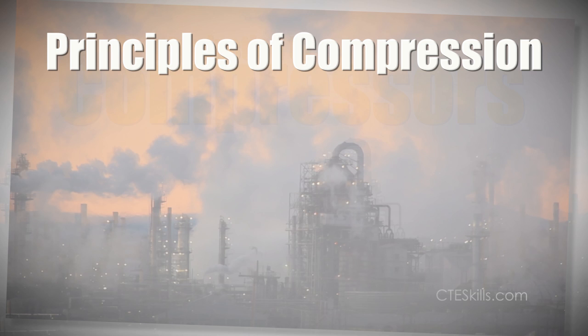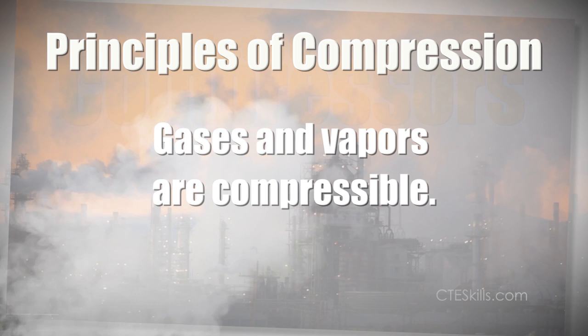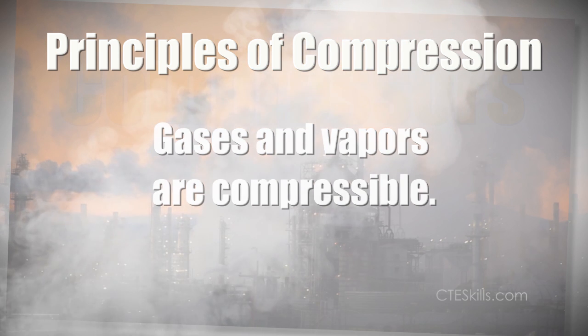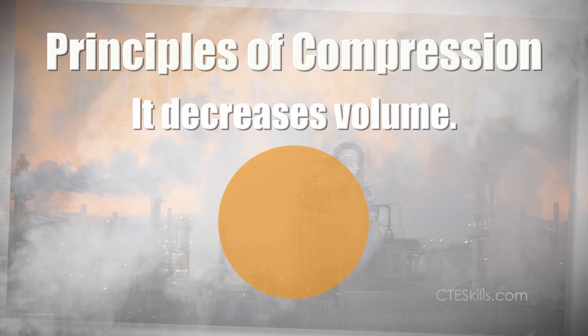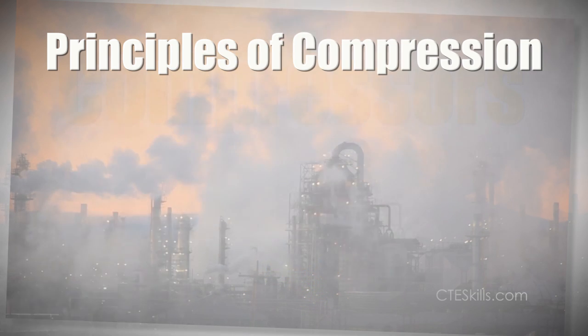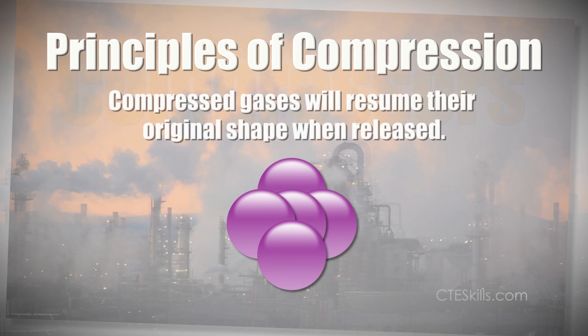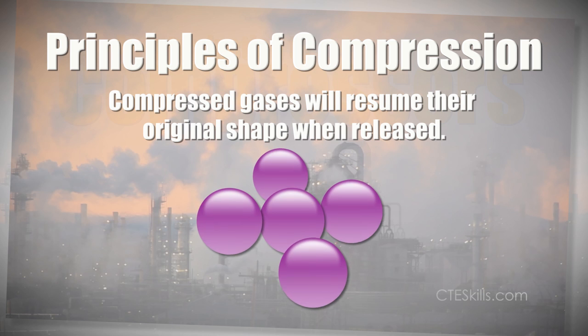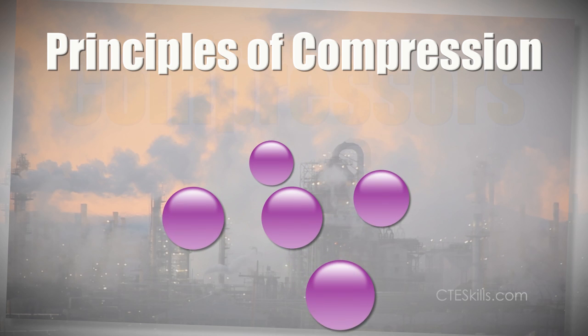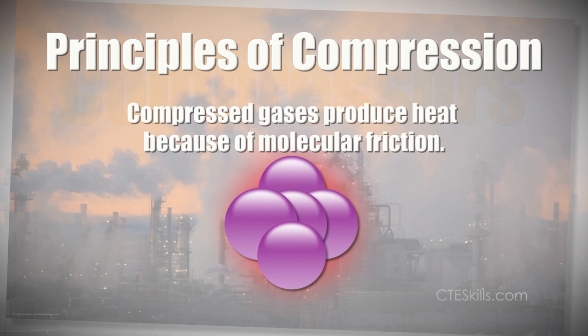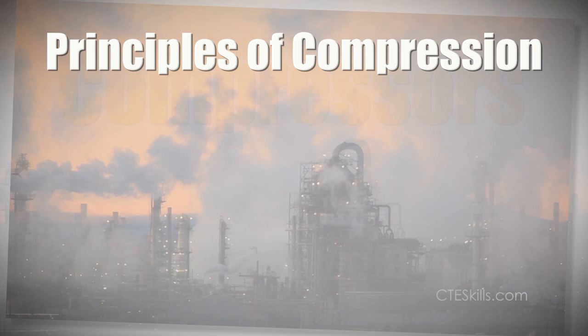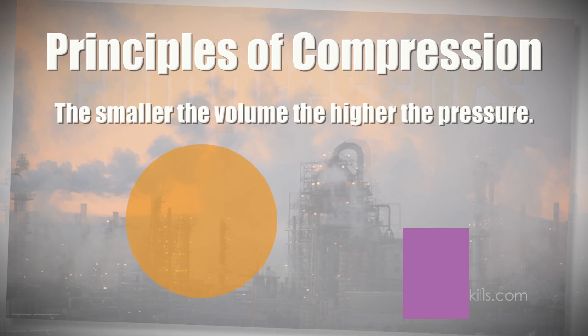Before we get started, let's go over some of the basic and fundamental points about compression. Gases and vapors are compressible. Compression decreases volume. Compression moves gas molecules closer together. Compressed gases will resume their original shape when released. Also, compressed gases produce heat because of molecular friction. The smaller the volume, the higher the pressure.